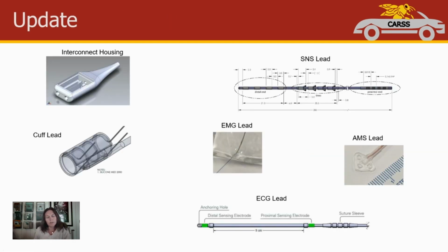Accompanying Nest 1, we are also developing materials for Nest 3. Nest 3 incorporates a series of standard leads to enable new research. Included in this list is an SNS, or sacral nerve stimulation lead style with 4 contacts, a cuff lead with bipolar electrodes, an EMG sensing lead, an ECG sensing lead, and an accelerometer-based motion sensing lead. All leads are to support the modular design and to allow for simple integration for each one. The lengths of each of these leads can be varied as needed. And additionally, there is an interconnect that will allow a 4-contact lead that connects to the header to split into 2 independent bipolar leads, allowing for even more versatility.